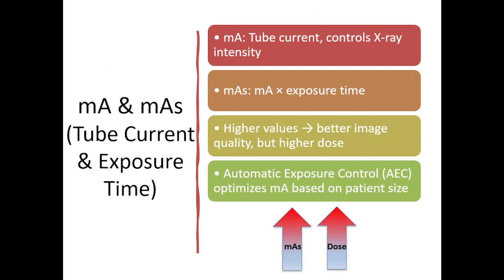mA represents the tube current, and mAs is the product of mA and exposure time in seconds. Higher values improve image quality, but also increase radiation dose. To balance image quality and dose, modern CT scanners use automatic exposure control, or AEC, which adjusts these values based on patient size.